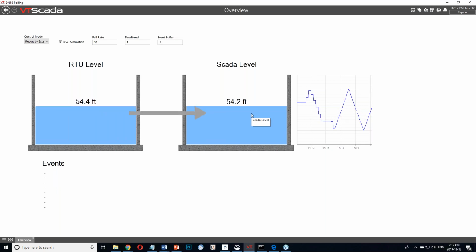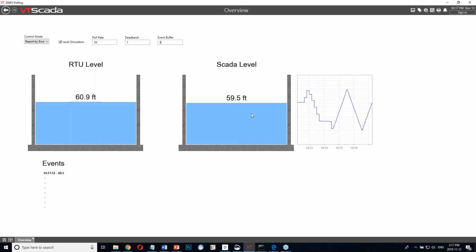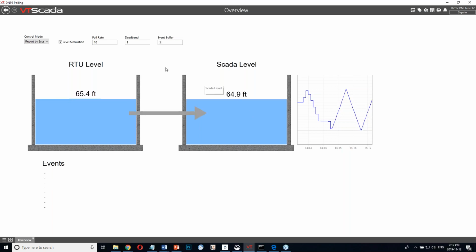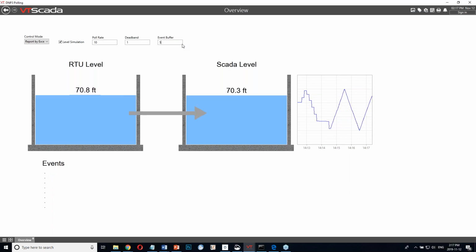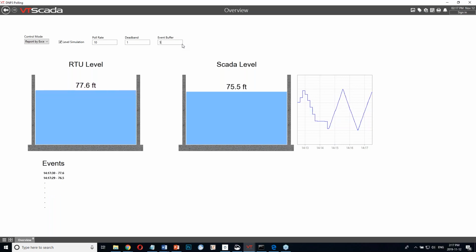And so there's a variety of schemes that people use with this in DNP3. Generally speaking, either individual I/O on the RTU will be able to have their deadbands or their event buffers or anything configured. Or sometimes the data is broken into classes, and we'll see that somewhat later, but it's mostly an organization thing. And again, this is an RTU side construct.